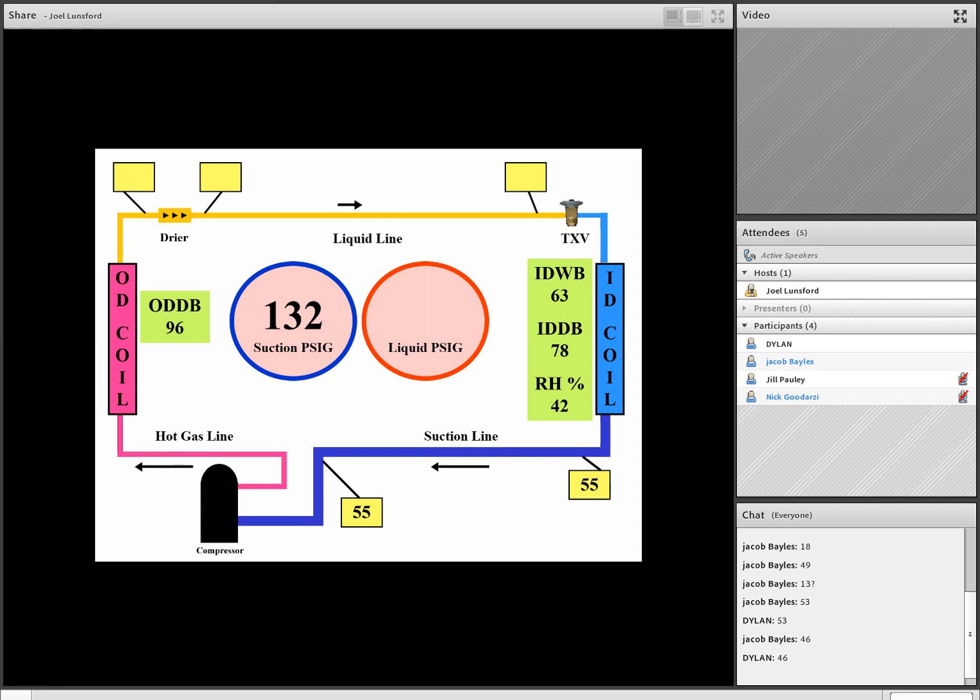So at this point, would you consider that coil flooded, starved, or normal? If we're supposed to have 10 to 15 and we've got 9 to 10, what would you consider the condition of that coil? It's close enough. That's what I say too. Thank you for that great observation. Team, if you're within 1 or 2 degrees of your chart or your target value, that's close enough.